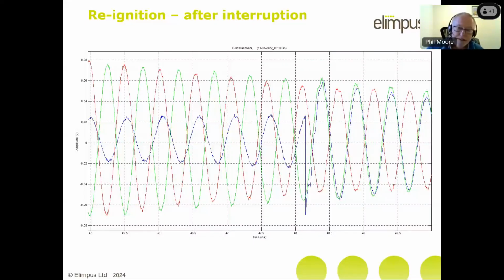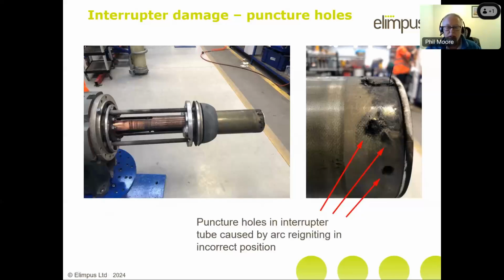And again, our friendly utility not only took it out of service, they took it apart and they showed us what they found. So let me show you this. This is the internal part of this GIS circuit breaker, quite an old design. The contacts are actually inside this glass fibre tube. One of the contacts moves on this sliding bit, and the fixed contact is removed, but it would actually be pushed in on the right hand side there.